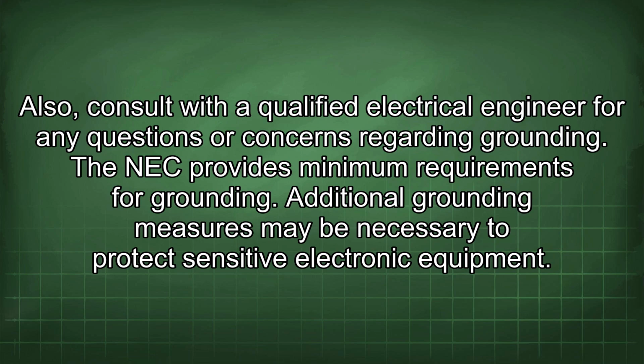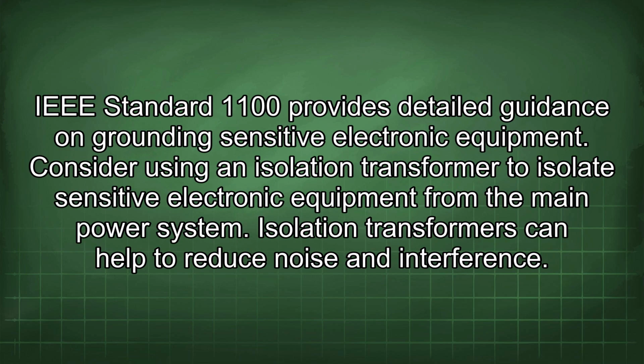The NEC provides minimum requirements for grounding. Additional grounding measures may be necessary to protect sensitive electronic equipment. IEEE Standard 1100 provides detailed guidance on grounding sensitive electronic equipment. Consider using an isolation transformer to isolate sensitive electronic equipment from the main power system. Isolation transformers can help to reduce noise and interference.